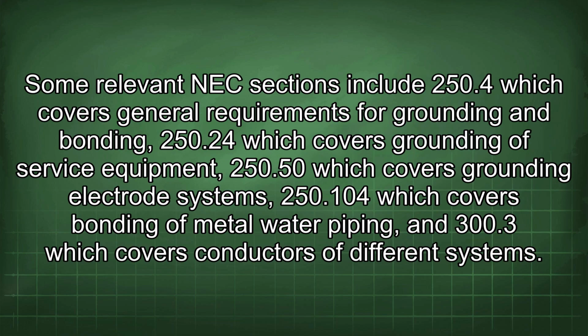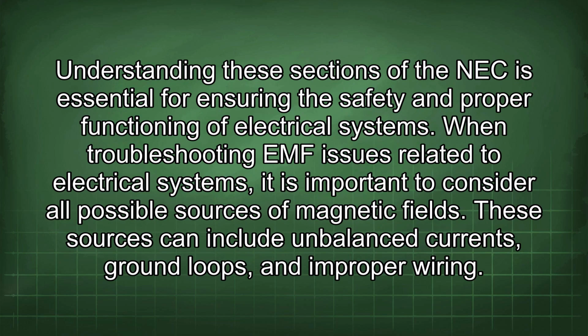Some relevant NEC sections include 250.4, which covers general requirements for grounding and bonding; 250.24, which covers grounding of service equipment; 250.50, which covers grounding electrode systems; 250.104, which covers bonding of metal water piping; and 300.3, which covers conductors of different systems. Understanding these sections of the NEC is essential for ensuring the safety and proper functioning of electrical systems.